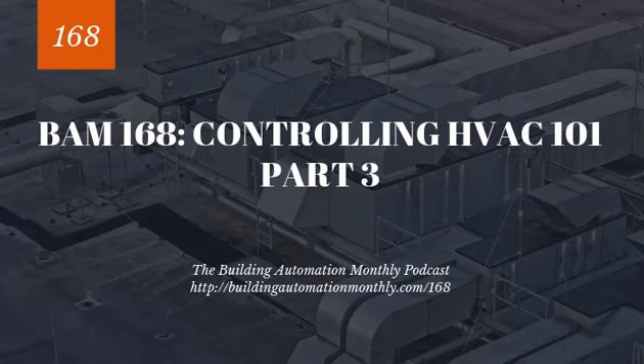You're thinking about this air handler, and it's got a cooling coil, and you've got this airstream, maybe a return airstream, coming into the cooling coil, and then that cooling coil has chilled water, and that chilled water is absorbing heat out of that return air path, and then that discharge air path on the leaving side of the coil is now colder, but the water leaving that coil is now warmer, and that warm water, as I said, returns to the evaporator.